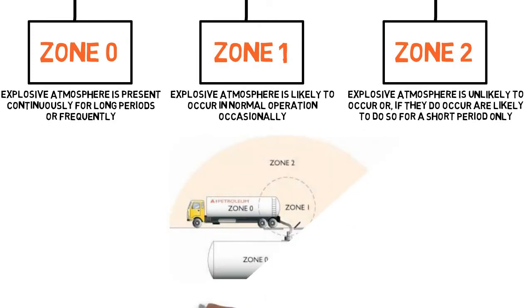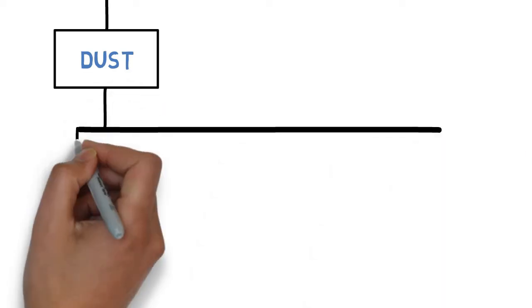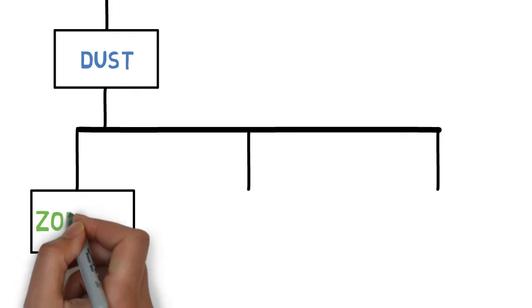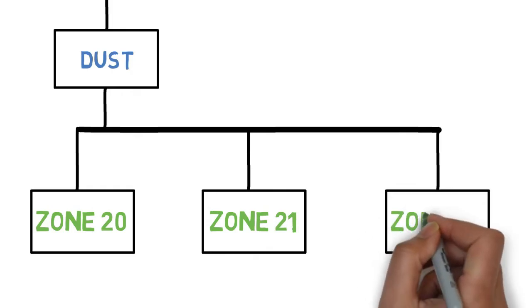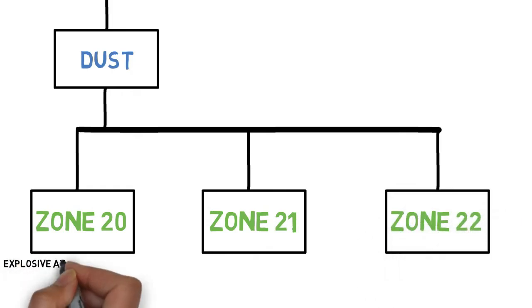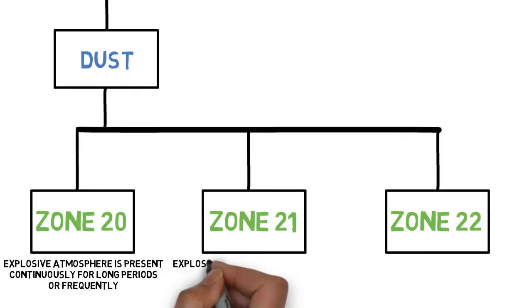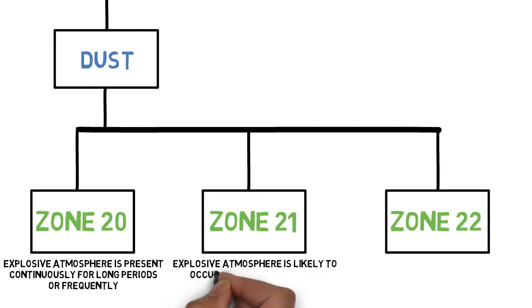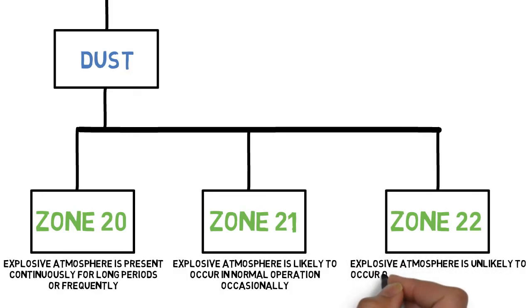From the image you can understand the zones. Similarly, dusts are classified into three different zones: Zone 20, Zone 21, and Zone 22. In Zone 20, Explosive Atmosphere is present continuously for long periods, or frequently. In Zone 21, Explosive Atmosphere is likely to occur in normal operation occasionally. In Zone 22, Explosive Atmosphere is unlikely to occur, or if they do occur, are likely to do so for a short period only.